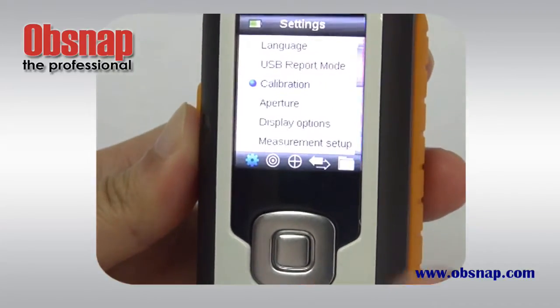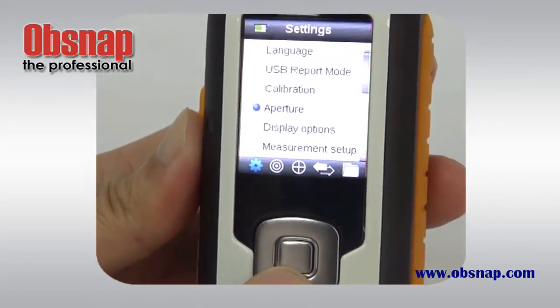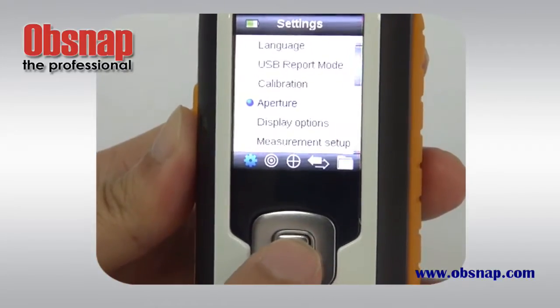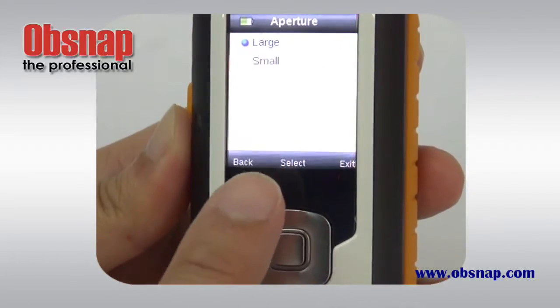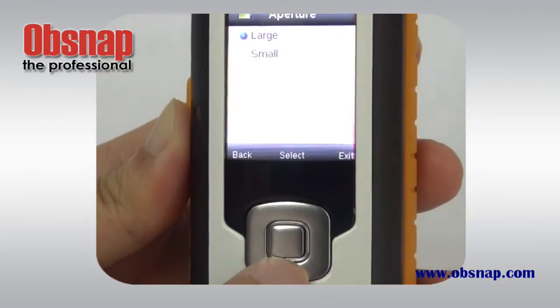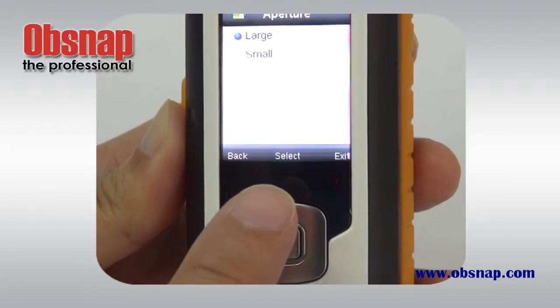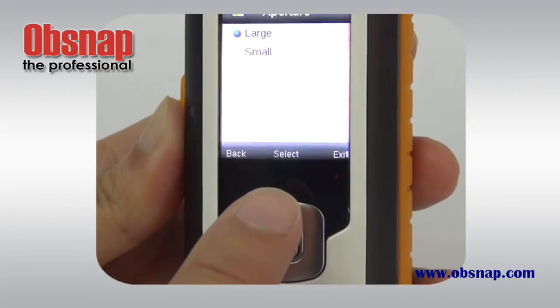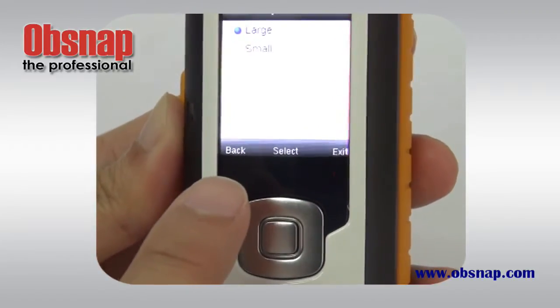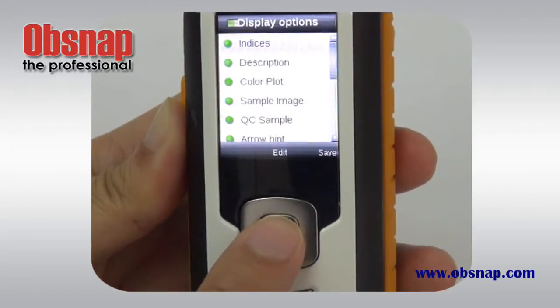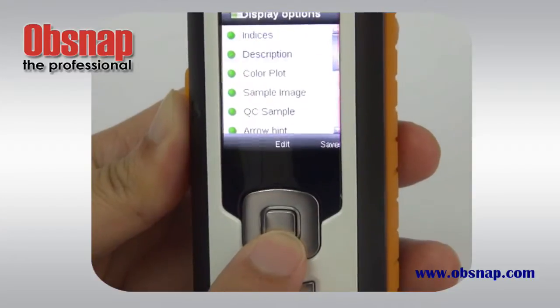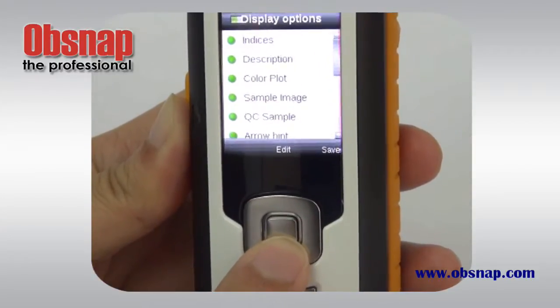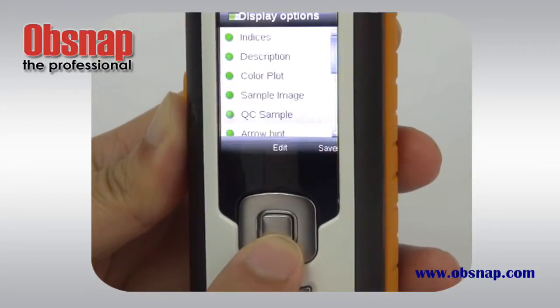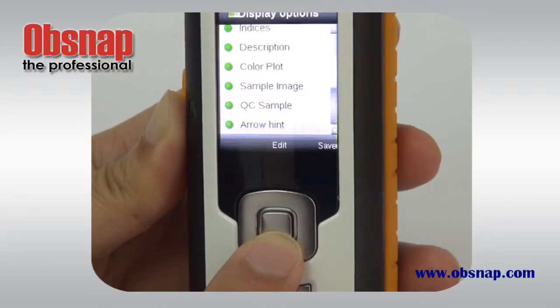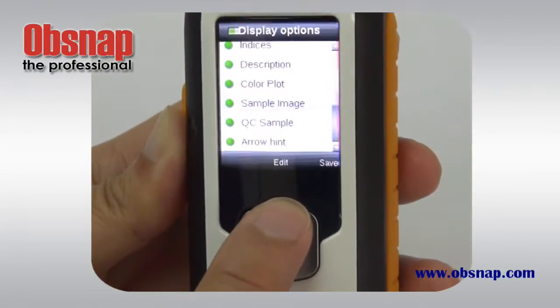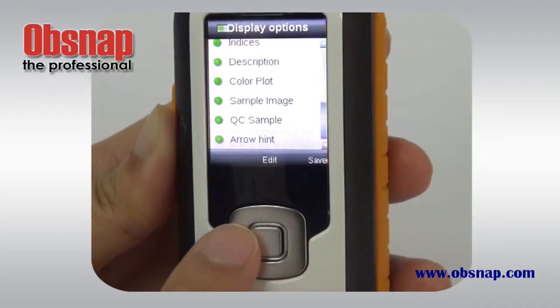Calibrations, we already did. Aperture: this unit is able to choose the large aperture size or the small aperture size. When we choose the large aperture size, the size will be 6mm, and the small aperture size is 4mm. The display options will be all color plot and all the information we can select. We can see all the QC samples, all the arrow hints, and all the data we want to see; we can select from here.